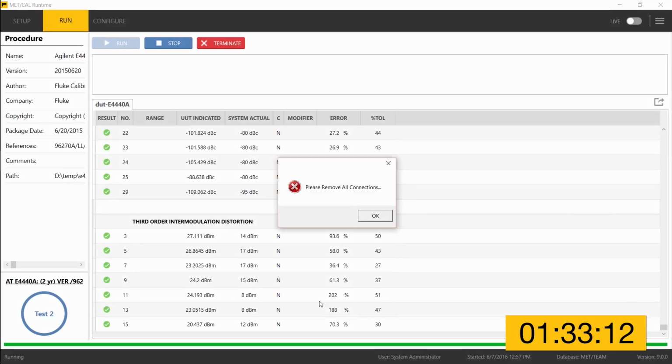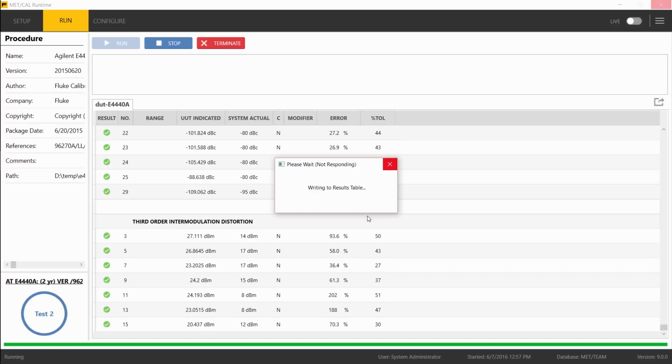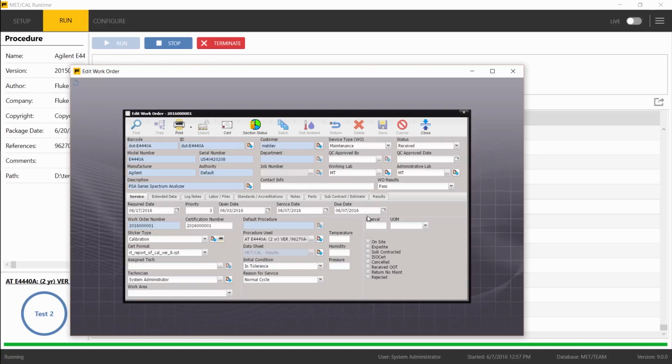All right, and that is the end of the procedure. I'm going to click OK here. This is the standard MetCal prompt to remove all connections. And what you'll see next is that the MET/TEAM work order will come up. That will give the technician the chance to fill in any additional information that's required, perhaps ambient temperature and humidity conditions.